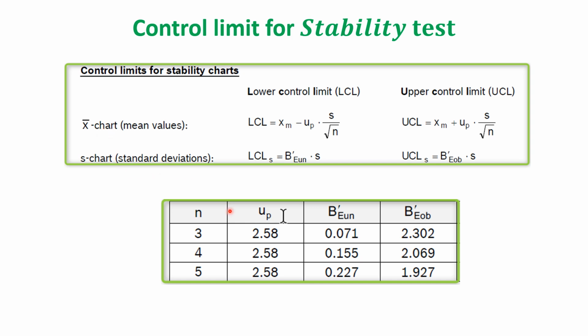As per the criteria we saw in the previous slide, you have to conduct the test again over a period of time. You take the reading and see whether it fits in that particular band. At the initial stage you draw the band, and later you only ensure the readings over a period of time are lying in the band. If it is lying in the band, then the stability test is okay. If it is not lying in the band, then the stability test is not okay.